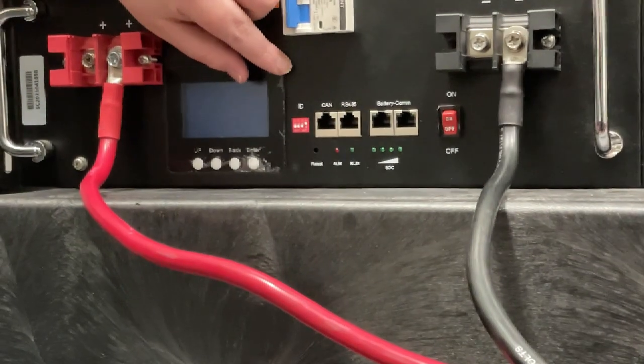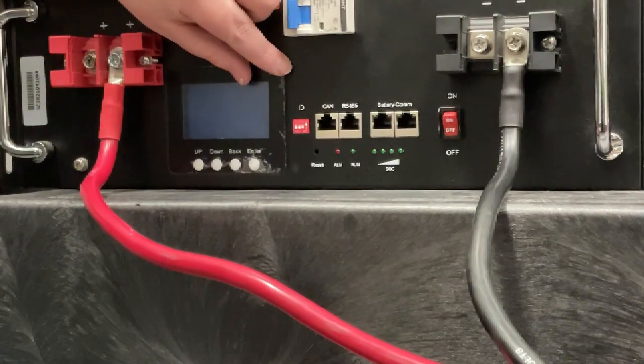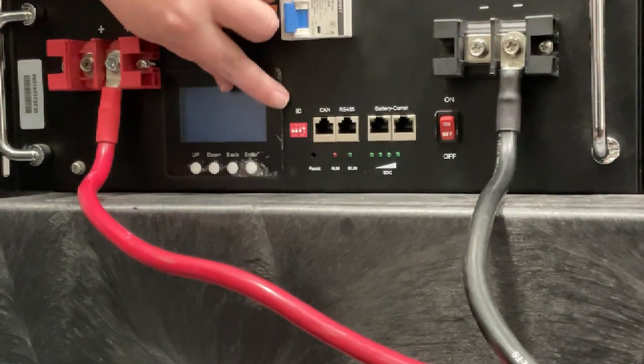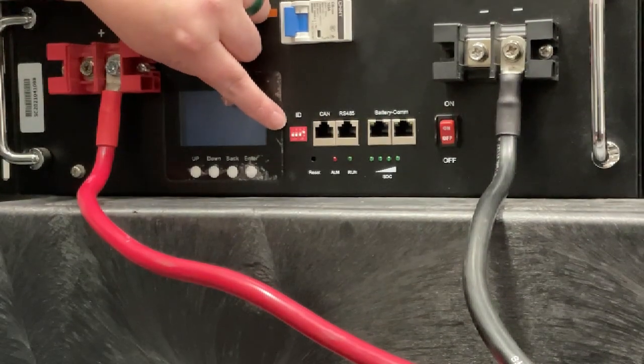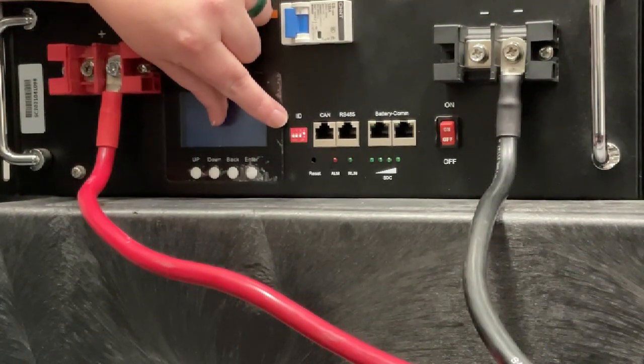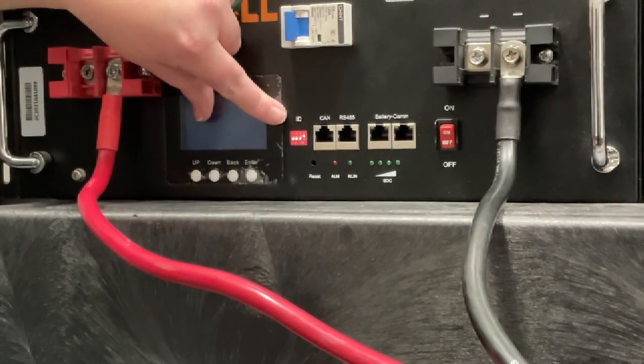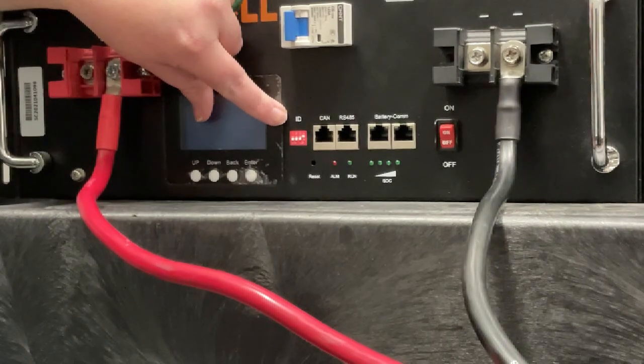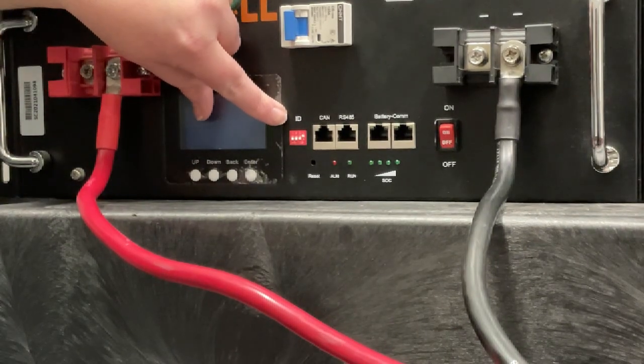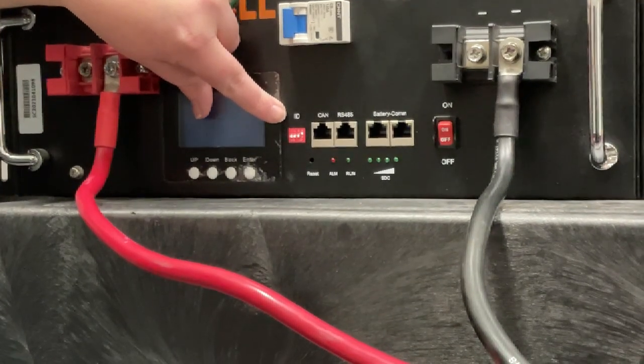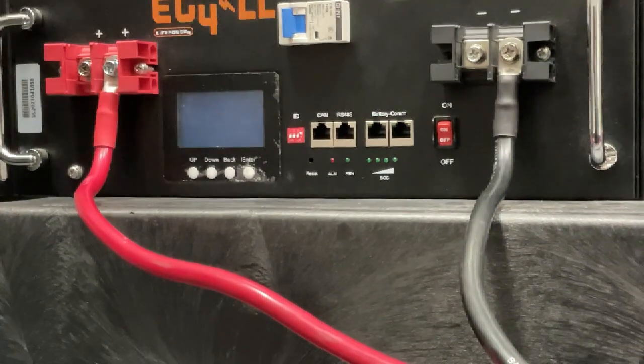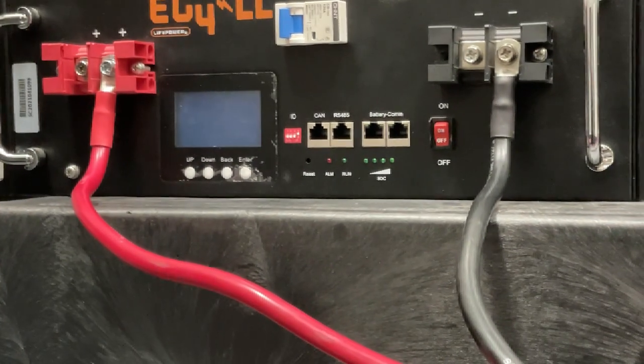So in the spirit of multiple batteries in your stack as well, your ID switches, your dip switches need to be different from one another. So if you had five batteries in your stack, your master battery, the one communicating with your inverter...